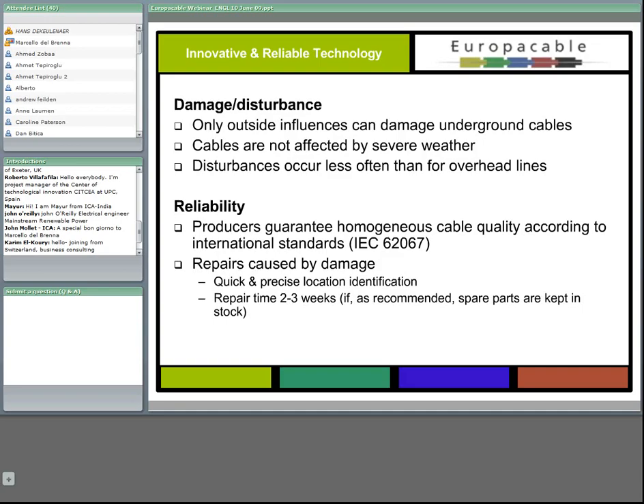Cable quality is guaranteed by testing standards developed in recent years. Repairs caused by external damage, after identification of the fault location, normally require 2 to 3 weeks if spare parts are kept in stock. The issue of spare parts has been recommended by the cable industry for a long time, and for key connections it is now the absolute norm.